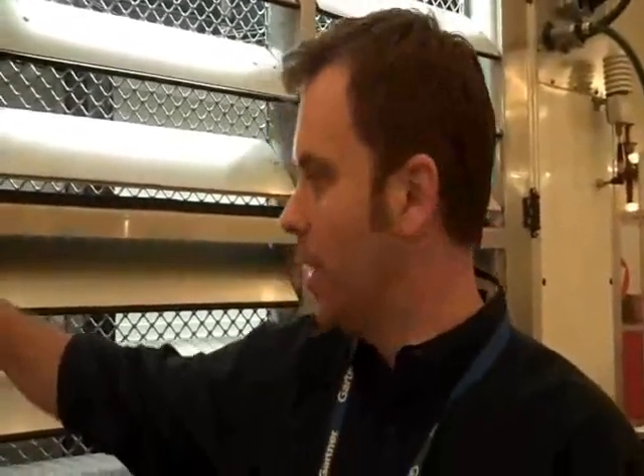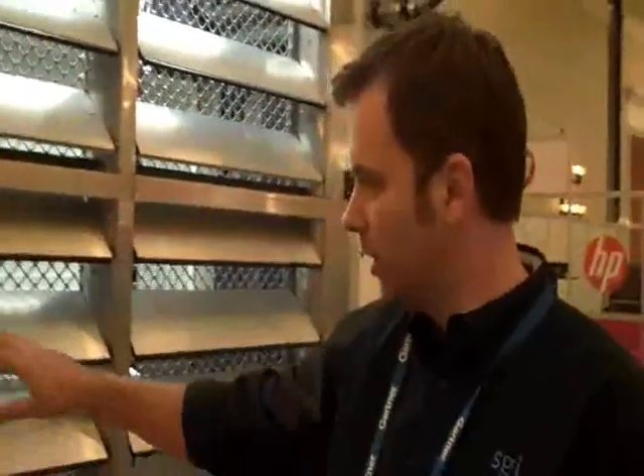If they have a chilled water system, they can add a chilled water valve in here and add a chilled water system into this. I'm not going to open this up today, but we'll give you a little insight. There's filters in here. You can add filters that are a distance away from the outside of the unit to keep the temperature up if it gets to the cold environments, to keep the filters from freezing.